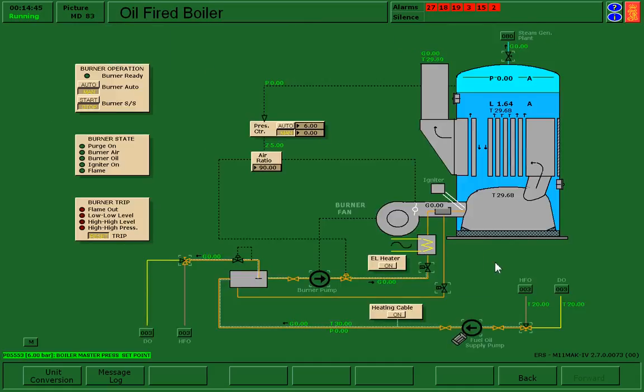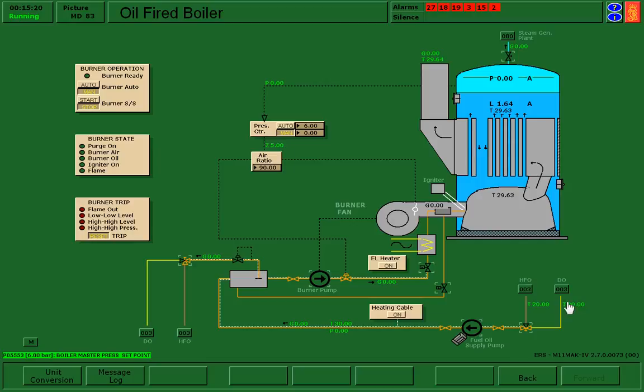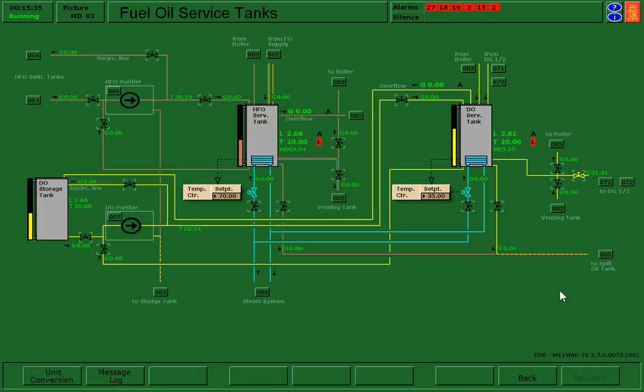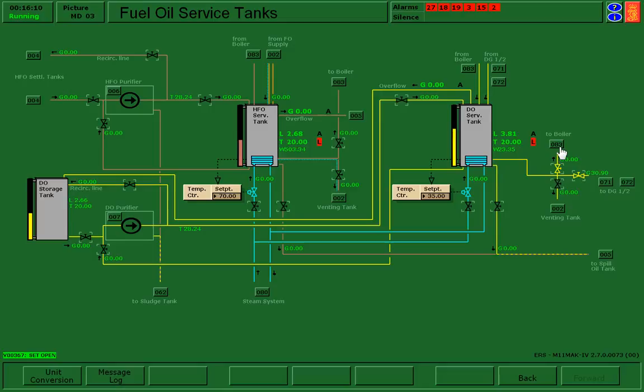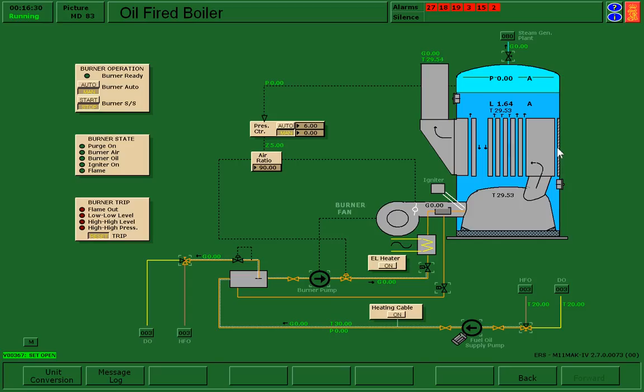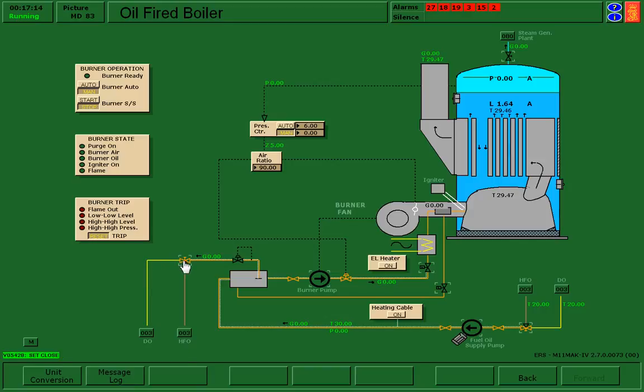In order to start up the boiler, I'm going to use diesel oil when it's first starting up. If we follow through our pathway for diesel oil, it starts from my service tank. Diesel oil service tank comes across up through to boiler, follows through my pathway to this tank where it then continues on. I want to switch over this valve so that I am returning any unused fuel into the diesel oil tank so I'm not wasting it.